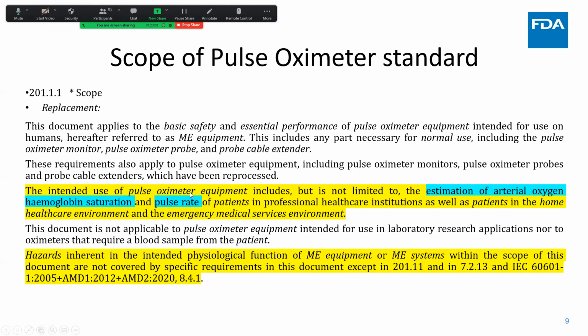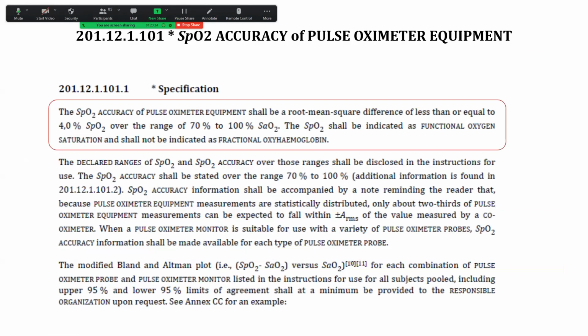Okay, so as Bob said, pulse oximeters are about the estimation of arterial hemoglobin saturation. It's an estimation, as well as pulse rate. And importantly, this little last clause in yellow says hazards inherent in the intended physiological function. This is trying to tell you that this is not a clinical practice guideline. This is about engineering the device to be safe. And so we talk about things like what is the accuracy and how do you measure it? And what are the constraints when one measures the performance of the particular device?